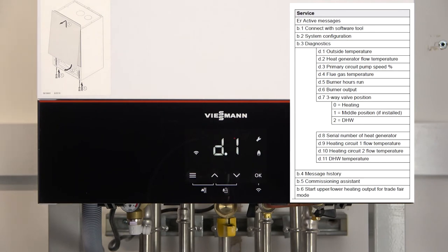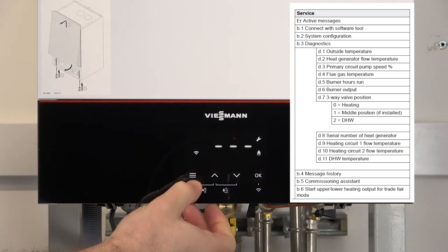As you can see within the shot in the screen, the D codes relate to what you're looking at within the boiler. So D1, for example, would be when we've got an outside weather sensor connected. So if you're running weather compensation, you'd be able to check what the outside temperature is and see if it correlates with the actual outside temperature, showing you if the sensor is in range. You can also actually check the sensors in range using your multimeter. If you haven't got a weather compensation connected, you'll see this display of dashes across the screen, showing that we haven't got one connected.